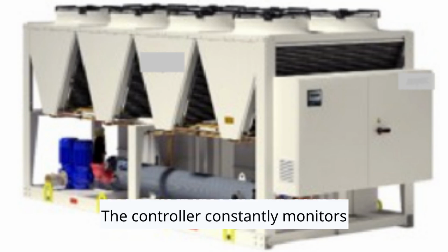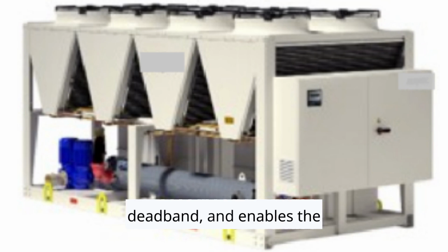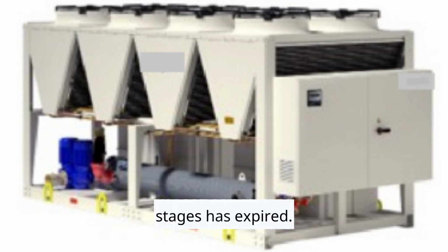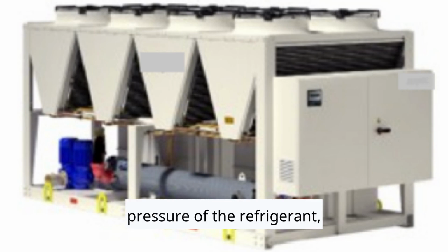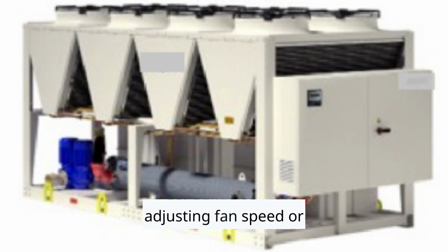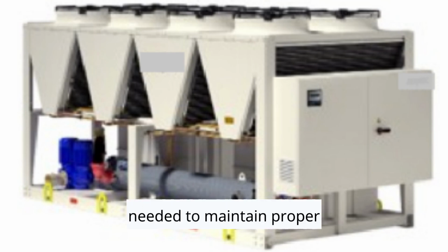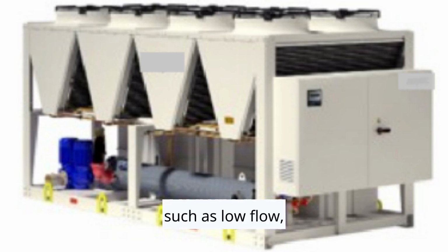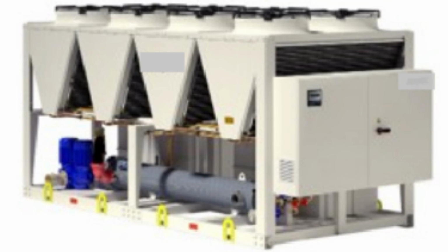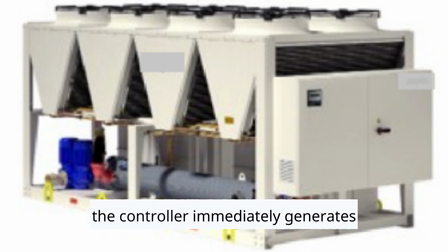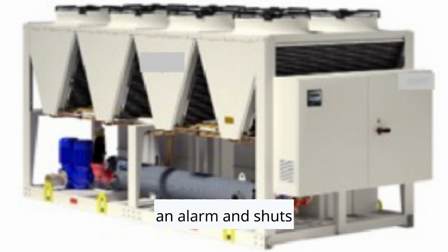The controller constantly monitors return temperature, set point, and deadband, and enables the next compressor only when the delay time between stages has expired. Meanwhile, it keeps an eye on the condensing pressure of the refrigerant, adjusting fan speed or water valve position as needed to maintain proper head pressure. If anything goes wrong, such as low flow, high pressure, low pressure, or a power issue, the controller immediately generates an alarm and shuts down the affected circuit for protection.